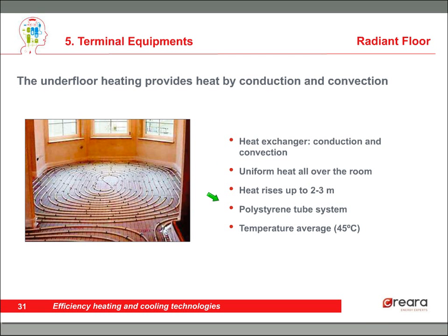It is very convenient because you don't have elements hanging on the walls, and it is made of polystyrene. And the wonderful thing is that they work with an average temperature of 35 to 45 degrees depending on the season. So it is very convenient, and it is really useful in residential buildings, office buildings, or even industrial buildings with high floors.